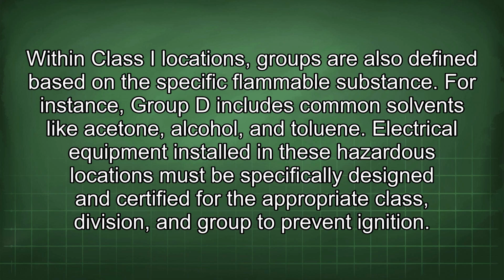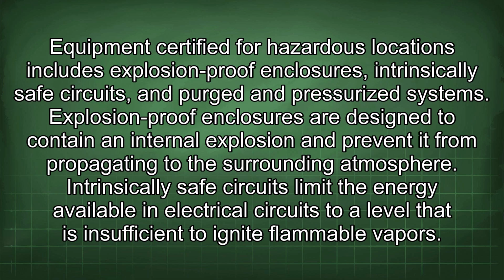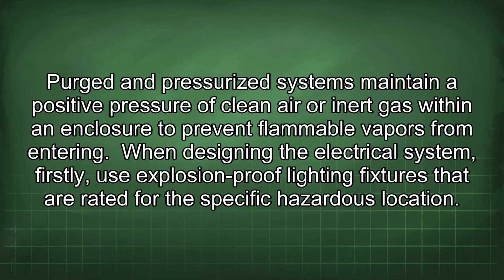Electrical equipment installed in these hazardous locations must be specifically designed and certified for the appropriate class, division, and group to prevent ignition. Equipment certified for hazardous locations includes explosion-proof enclosures, intrinsically safe circuits, and purged and pressurized systems. Explosion-proof enclosures are designed to contain an internal explosion and prevent it from propagating to the surrounding atmosphere. Intrinsically safe circuits limit the energy available in electrical circuits to a level that isn't sufficient to ignite flammable vapors. Purged and pressurized systems maintain a positive pressure of clean air or inert gas within an enclosure to prevent flammable vapors from entering.